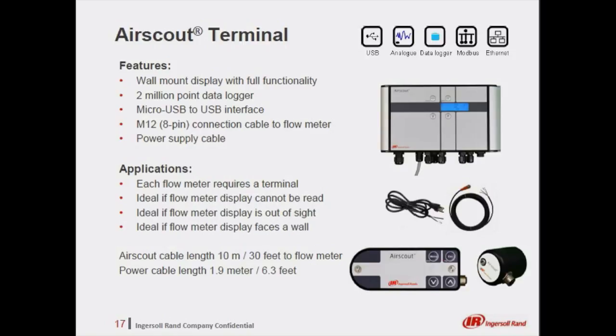The Airscout Terminal is a wall-mount display with the same functionality as the point-of-use displays and includes a 2 million data point logger, as well as a micro USB to USB port for direct connectivity to a computer for download of data for analysis. The terminal includes a 30-foot connector cable and a 6-foot power cable for use when it's not being hardwired into a system. An Airscout terminal would ideally be needed for each flow meter that requires a wall mount display, and the terminal is ideal when the display can't be read at the point of use or when the installation of the flow meter may face a wall.